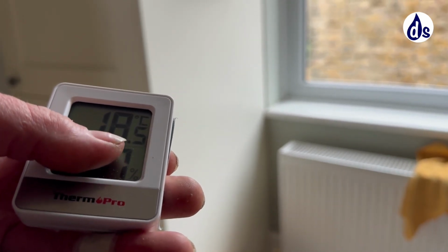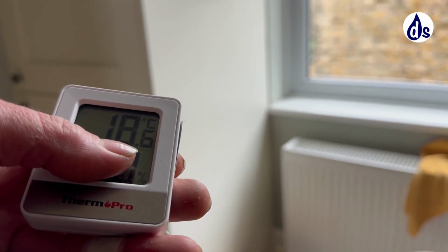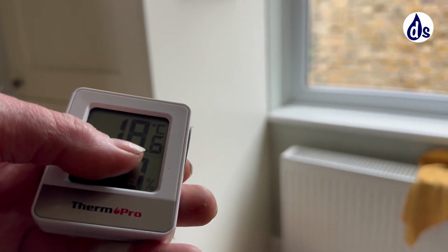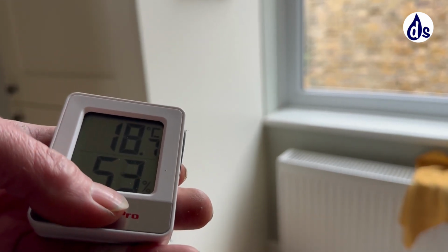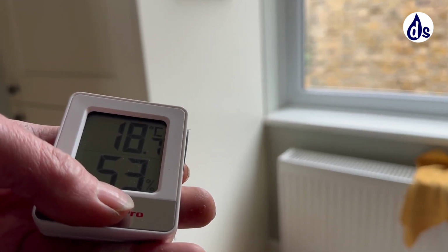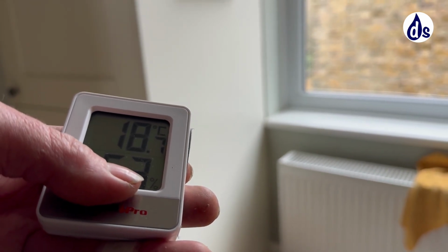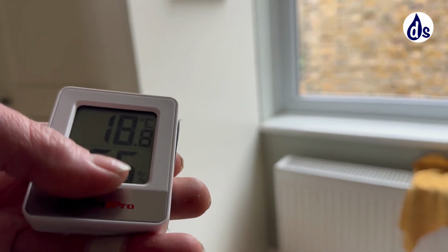And I would say the inside wall is about 7-8 degrees centigrade. And I'm going to go and have a look. Yeah. So that 10 degrees centigrade drop in temperature will increase the relative humidity by about 50%, 5 times 10. So for every drop of 1 degree centigrade, it increases relative humidity by about 5%.